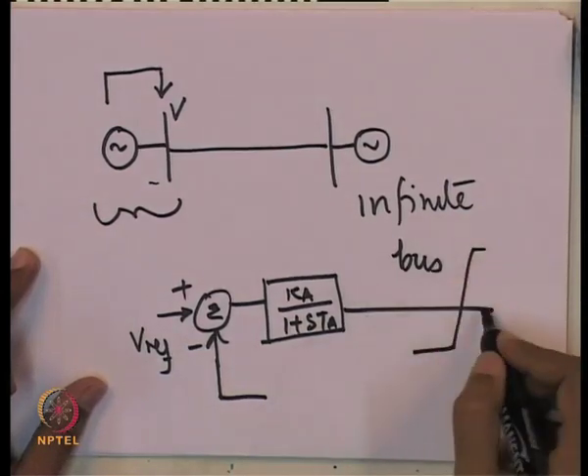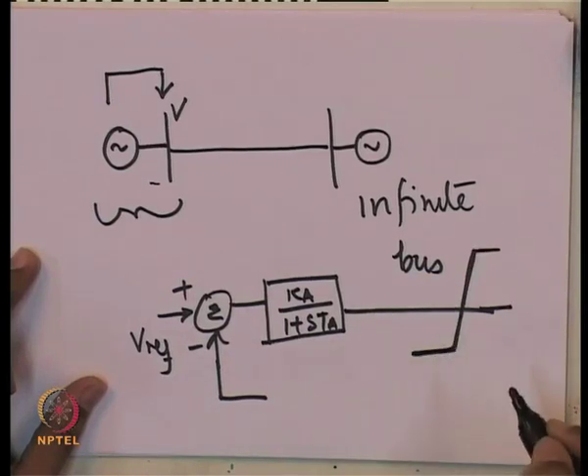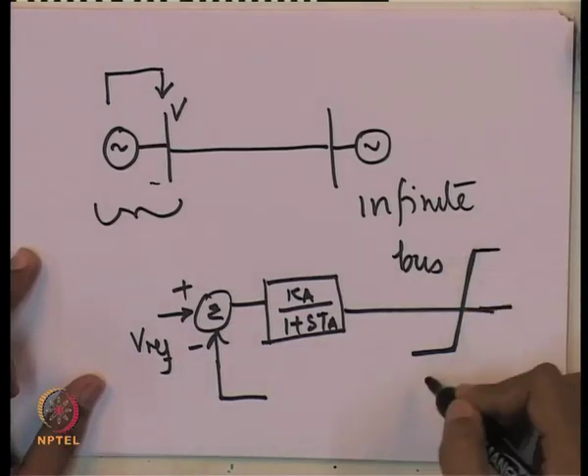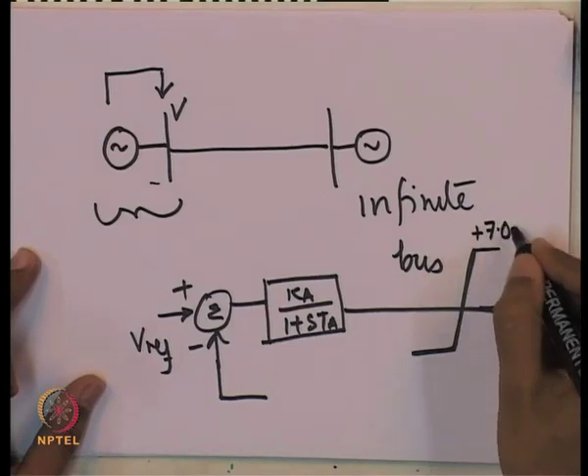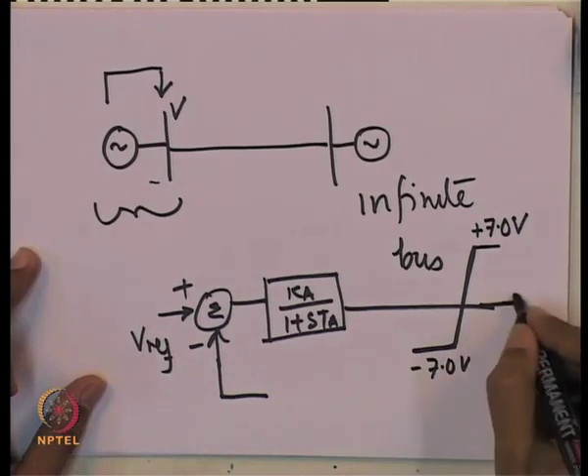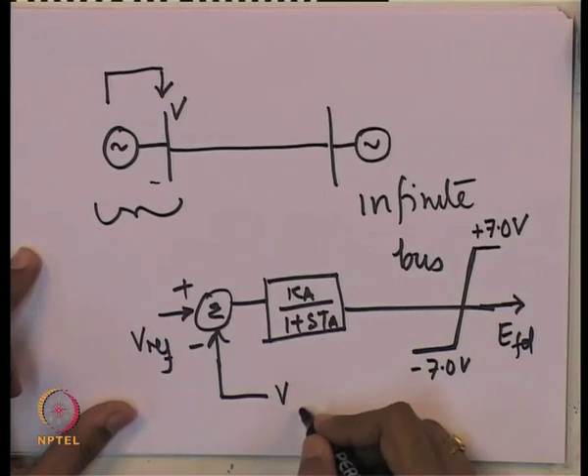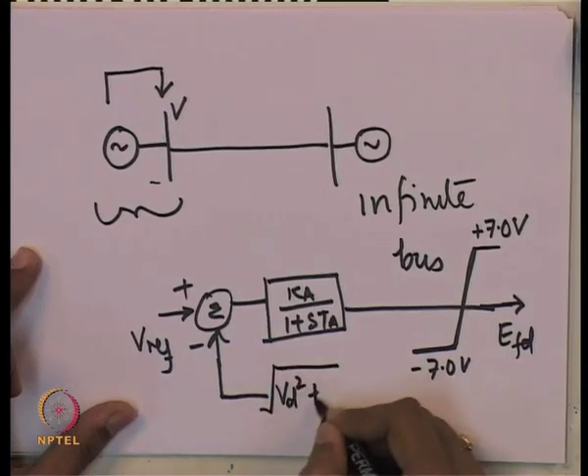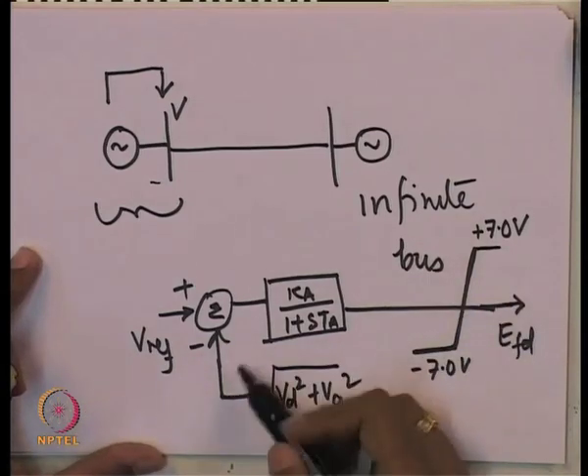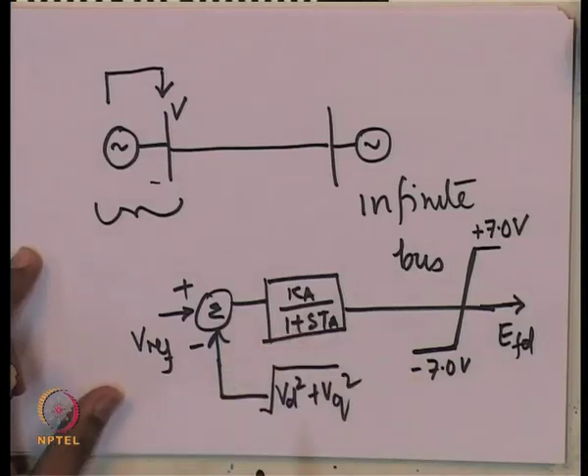The model with normalized quantities is simply a plant with a gain of one, and the limits of the static excitation system are taken into account. The feedback is the magnitude of the voltage, which is the square root of Vd squared plus Vq squared. We assume there is no measurement delay here, though we could model this delay by a first-order transfer function if we wished.